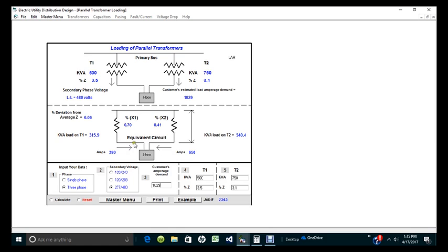You'll see here that we still have our same load flow. And the first transformer, T1, has a load of 380 amps and the second 650 amps. Well, what that really all tells us is that it's okay in an emergency situation to go ahead and put the 750 in and replace the 500 that had begun to leak out in the field.